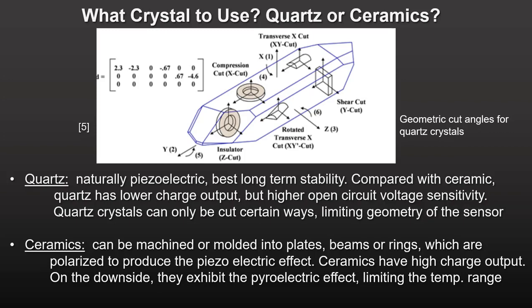The original piezoelectric accelerometers used quartz for the sensor element. Quartz has the best long-term stability and does not exhibit the pyroelectric effect, meaning it does not generate spurious voltage when heated or cooled. On the downside, quartz has lower charge output than ceramics and high open-circuit voltage sensitivity. Its biggest disadvantage is that it can only be cut in certain geometries, limiting sensor designs — a problem somewhat similar to producing diamond jewelry, but at a much lower cost.